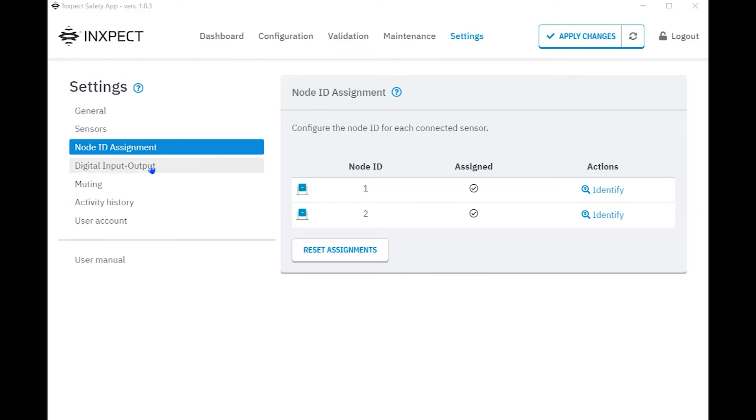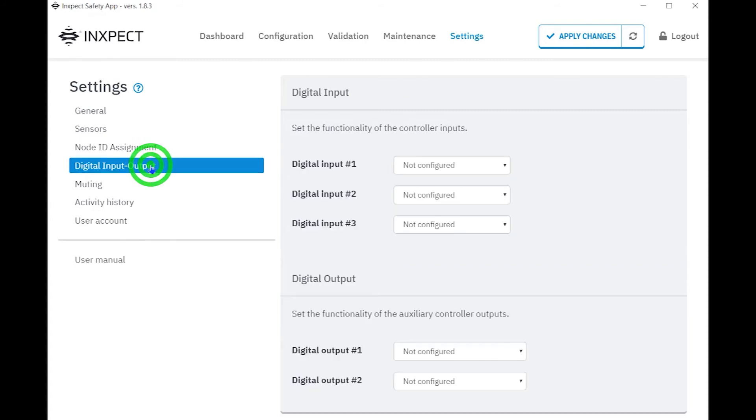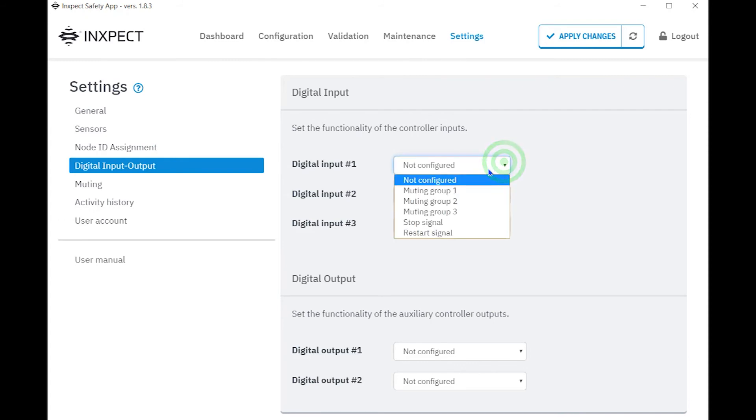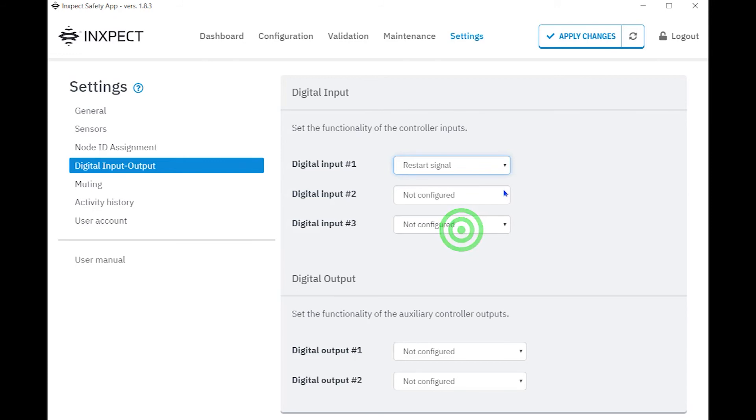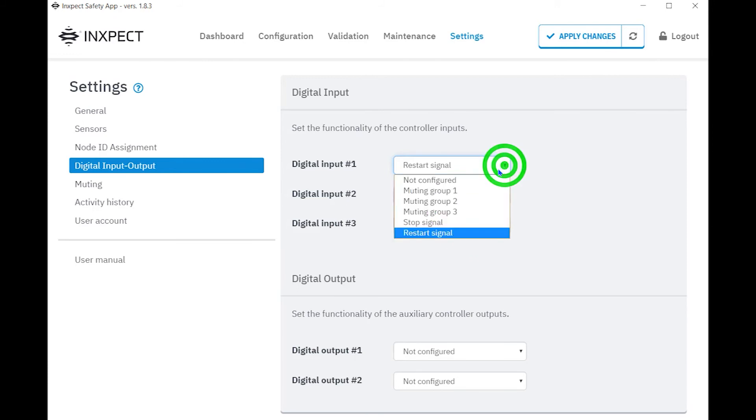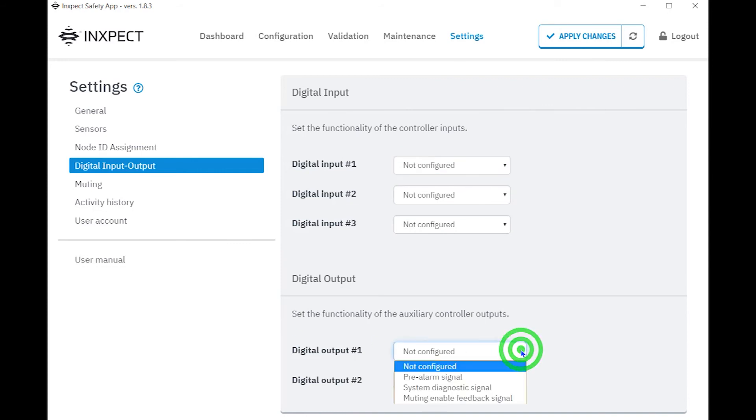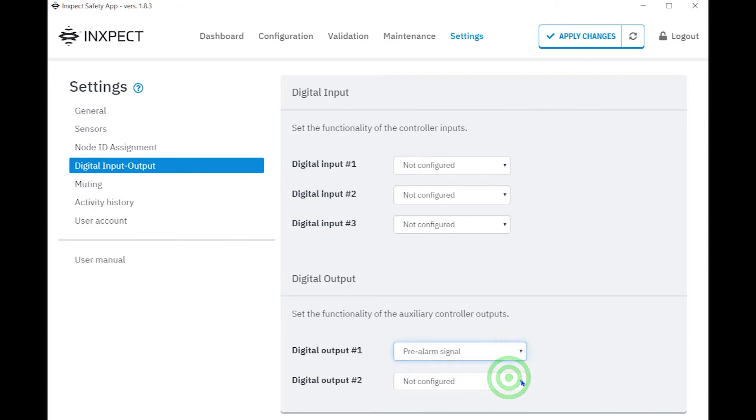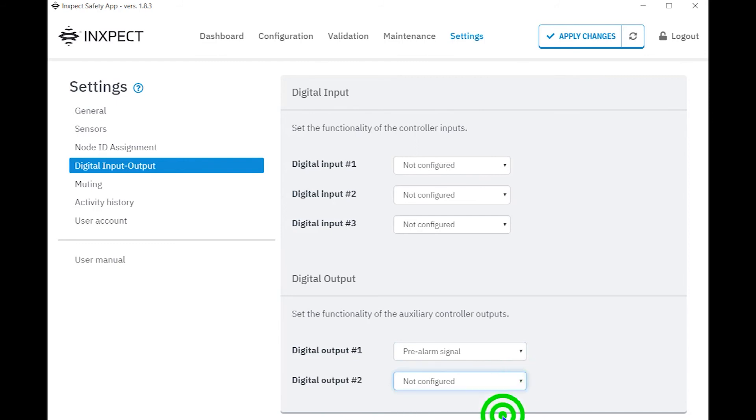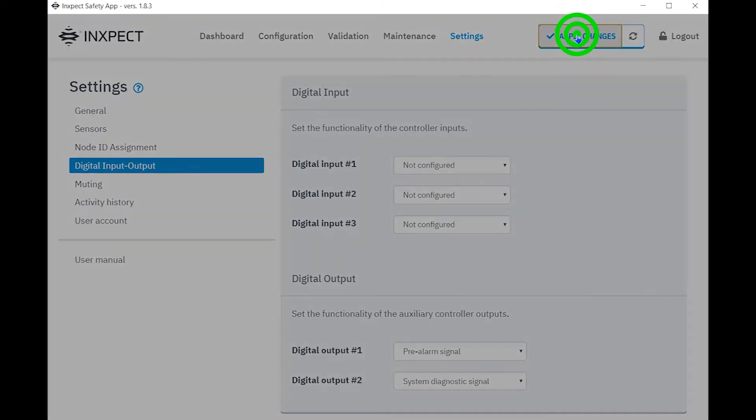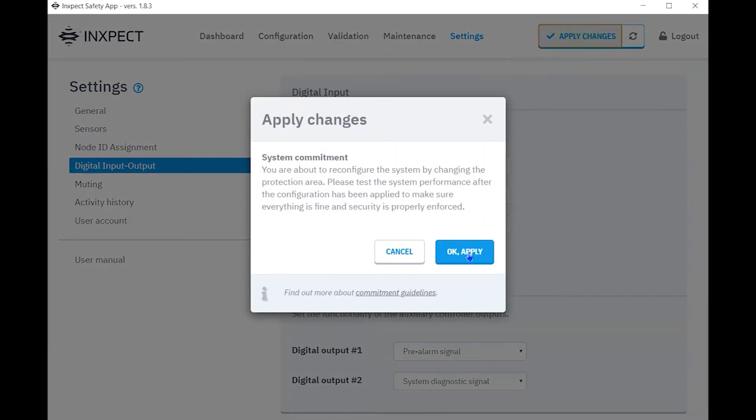The final item to be configured for this application is the I.O. This is done by clicking digital input output tabs in settings. If we wanted to use manual restart or provide muting capabilities, those input options are set here. For this configuration, we're going to use auto restart. For the outputs, we're going to set output one to be enabled when there's motion detected in the pre-alarm area and output number two to be enabled when there's a system fault. We click apply changes to load these final settings into the controller.